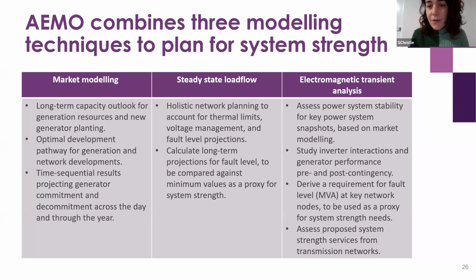We also study inverter interactions and generator performance pre and post contingency. That process is where the minimum fault level requirement is derived at particular network nodes that are selected as study points so we can focus the work and effort, known as system strength nodes. Finally, we also use electromagnetic transient analysis to analyse whether or not the services being offered by the transmission network or the non-network providers are actually going to address the need and the problem.